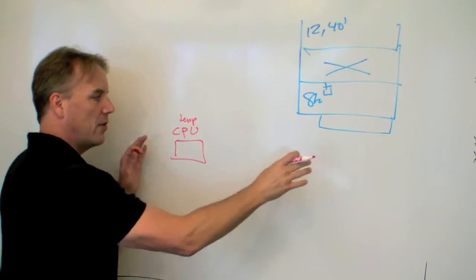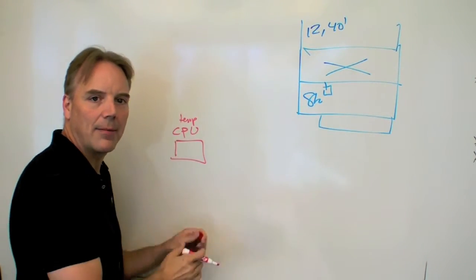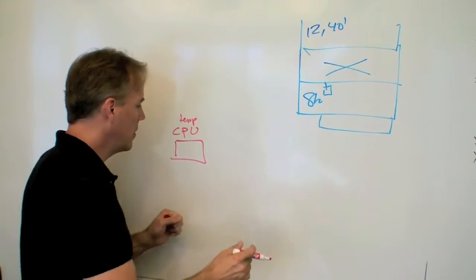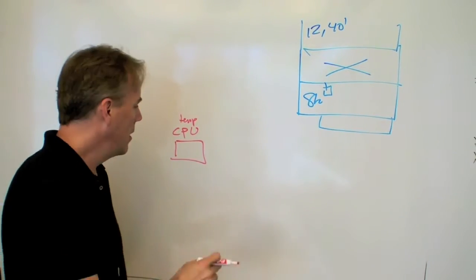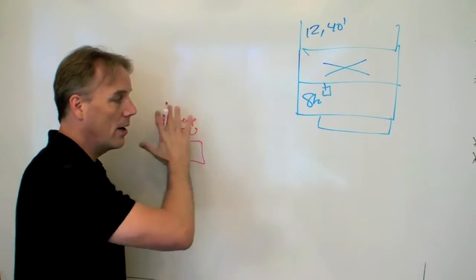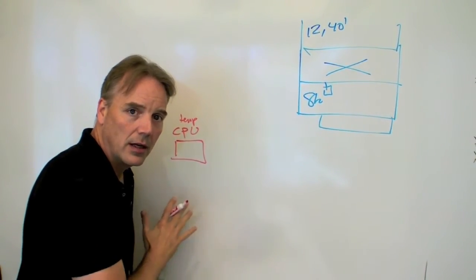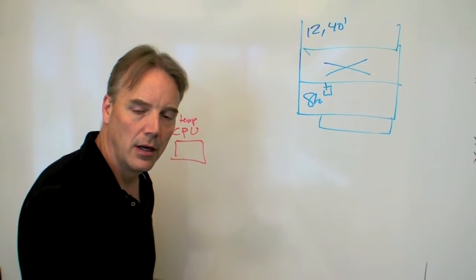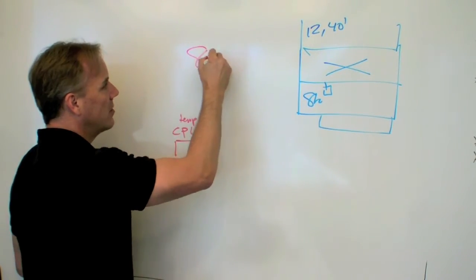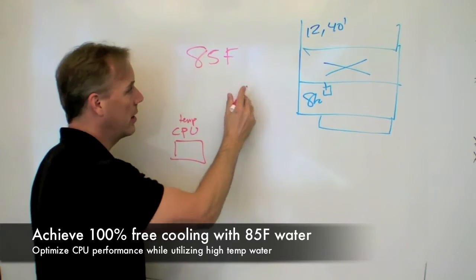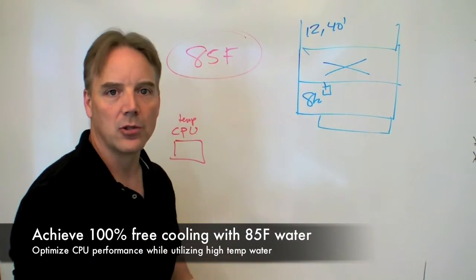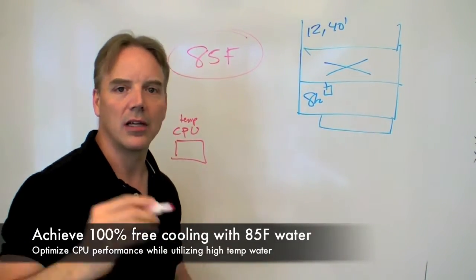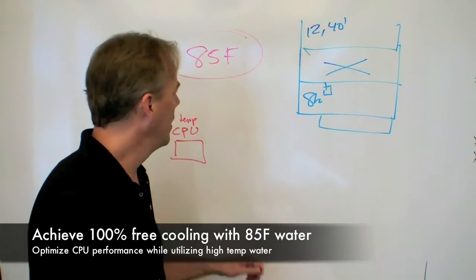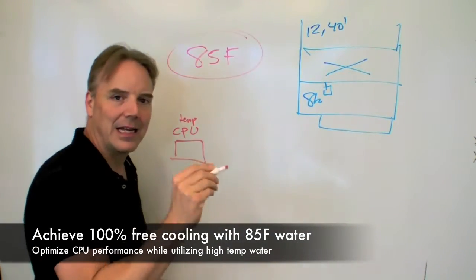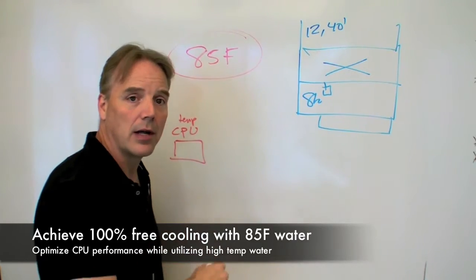How do I now say those two dictate everything else that happens around it? So the maximum temperature I can run these CPU systems at, I want 100% free cooling in Arizona year-round. What we found is 85 degrees Fahrenheit for the water is the maximum wet bulb temperature we have to actually cool for in Arizona, even if it's 130 degrees outside. The key being, that will be the inlet temperature for the ultimate end state products.